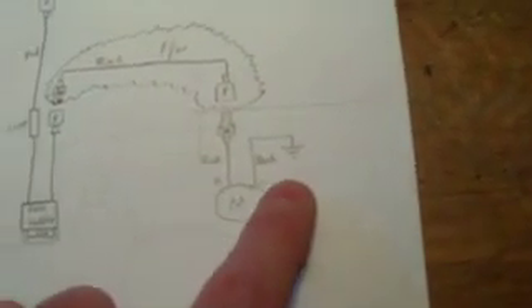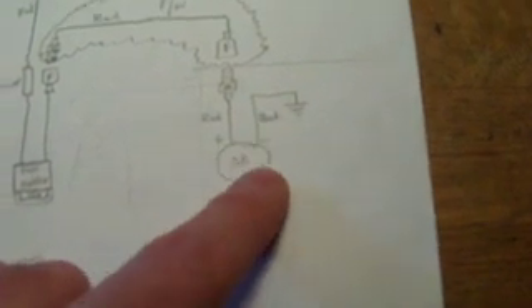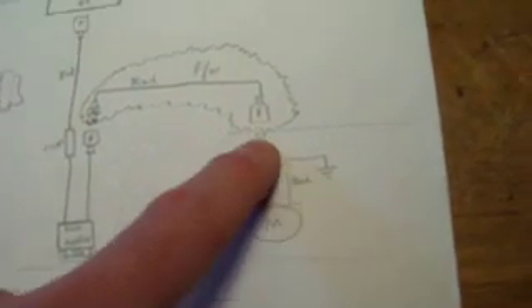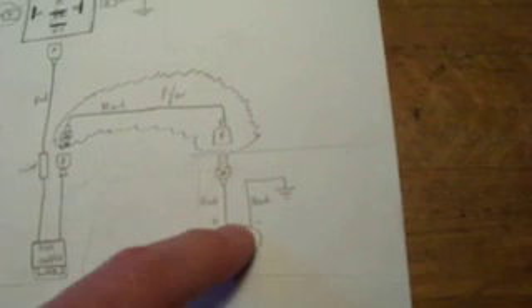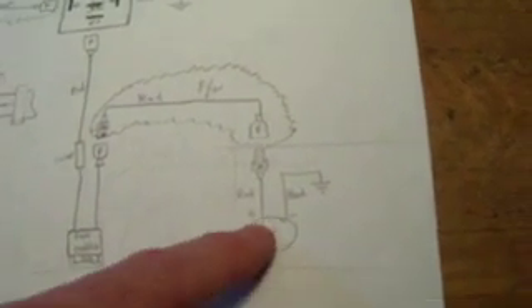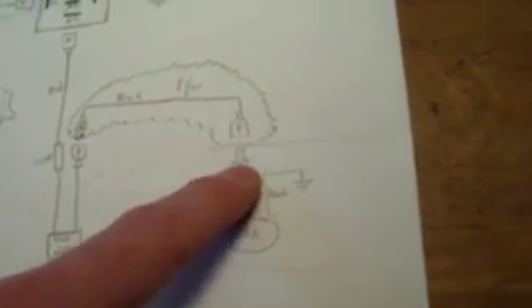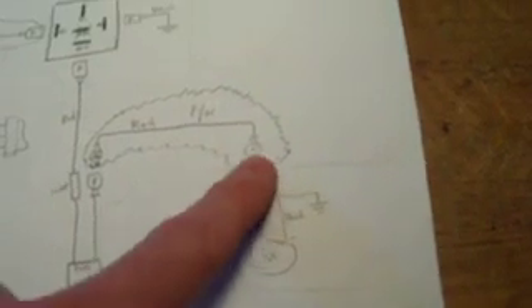Okay, here's a little different way to look at it. As I was working out the details of wiring it up out of the motor, I ran a black wire to chassis ground for the negative, and came up through here. I've got a quick disconnect in case I have to replace the pump motor at some time — a male connector coming off here, a female connector, and that's all taped down.